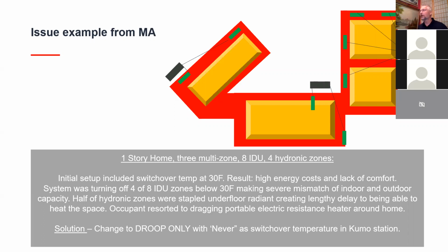So here's a house in Massachusetts. We ended up doing a site visit to this one to try and figure out what the heck was going on. The owner of the house, who was a tenant living there, was complaining broadly and widely that heat pumps don't work at colder temperatures. But the reason it wasn't working is because the system was configured to shut off 4 of 8 zones of 3 multi-zone outdoor units anytime it dropped below 30 degrees Fahrenheit. And the installer was completely just following the guidance of the program in Massachusetts in order to accomplish this.